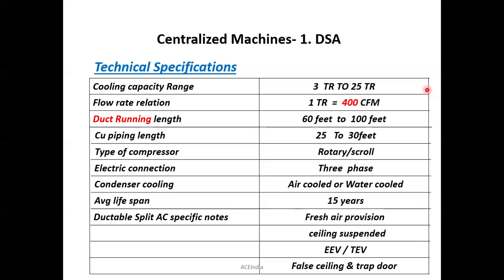But typically in India, we can simply go with an air-cooled condenser, where you can see the tonnage range is up to 25 ton itself, not saying beyond 100. So typically for DSA, ductable split AC connections, the available capacity range is mostly between 3 and 25. That is the max spec. If it goes beyond 25, we will not install it on the ceiling. It should be shifted to the floor.